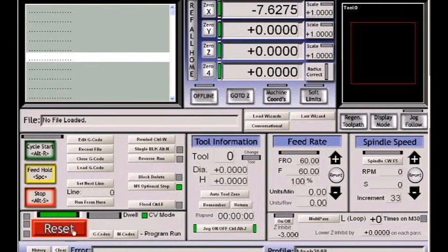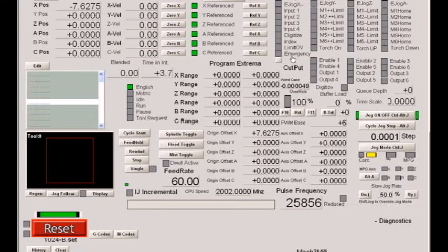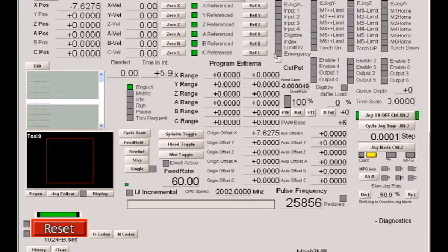You can always check to see if a signal is interfering with you by going to the diagnostics page, and if this emergency input was blinking, it means that the active low setting is set incorrectly and it is seeing an emergency stop.